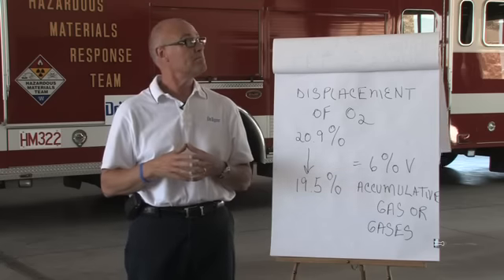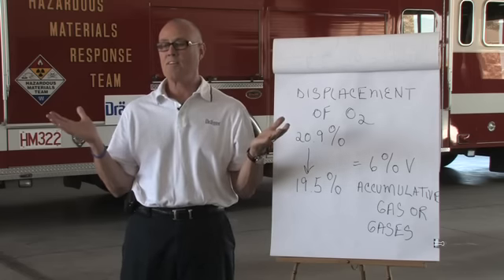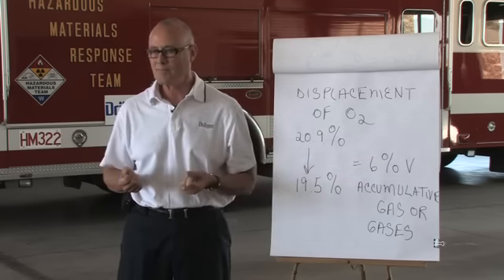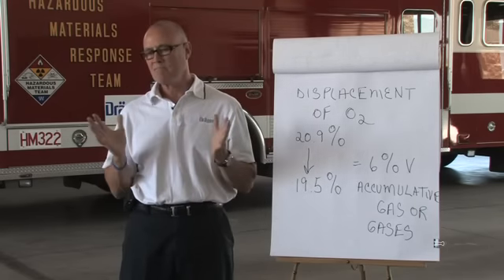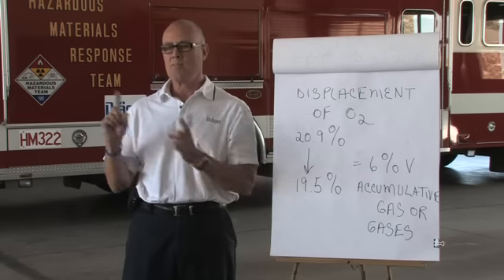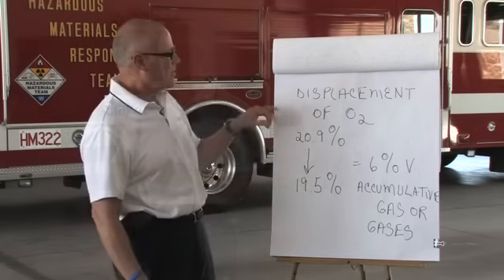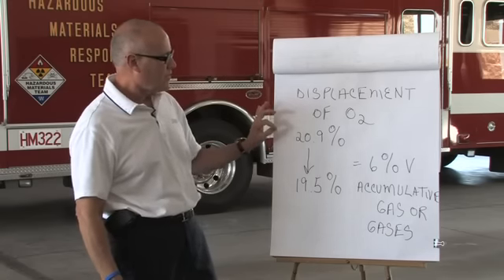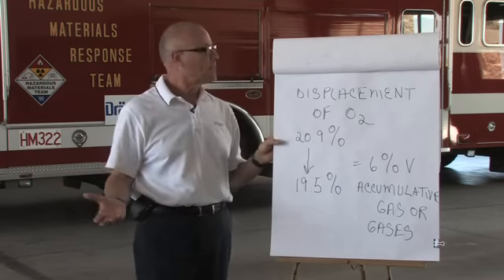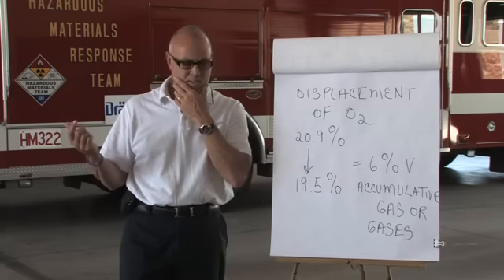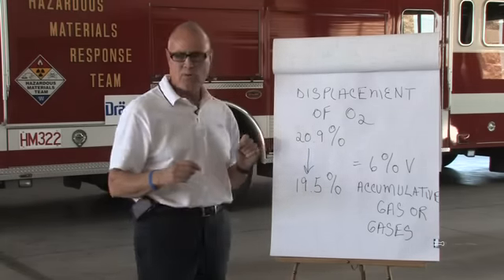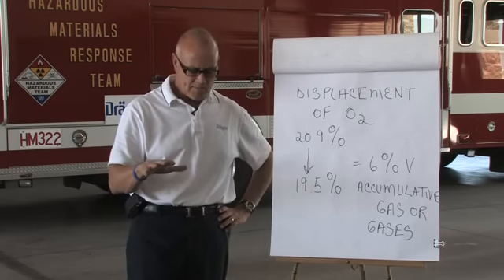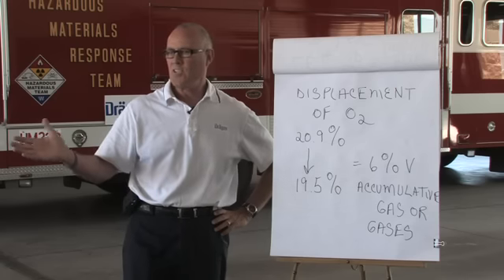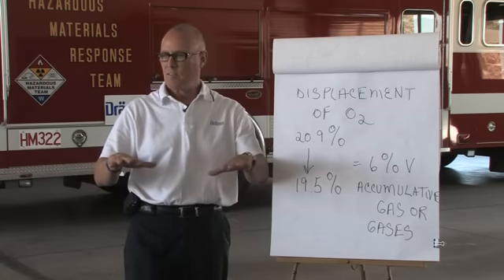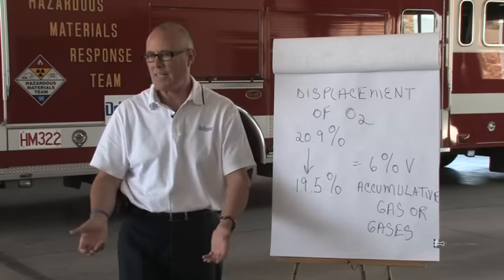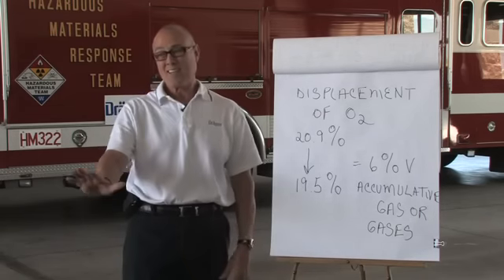But if you're in a structure on startup, it's possible. It could be that there's some gases there that have displaced the O2 that your instrument can't detect. And you can't detect it with your nose because it doesn't have a warning property. It's a hypothetical, but when in doubt, take your instrument outdoors and perform a fresh air calibration. What you've got here is what's causing a deficiency when you walked into a space. Generally, when you're walking outdoors or you're walking to a structure, your oxygen content generally doesn't change much. It's when you get on a space or come upon a space that's a tank, a vessel, it could even be a ditch. A ditch is even a confined space, because if there's no air movement and everything is settled, you could have inert gases in a ditch that you don't know about that are much heavier than air. Sounds kind of odd, but it's true.